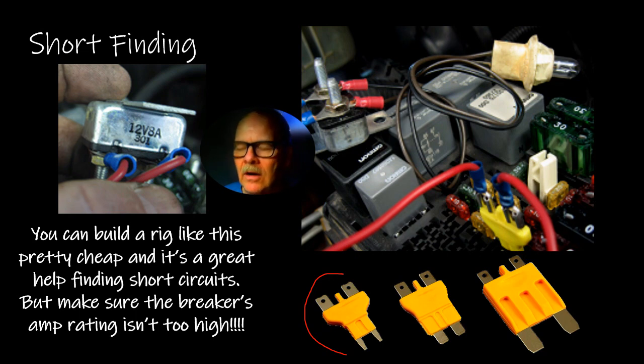The way that works is you connect a light bulb to these two terminals, and you connect these two terminals, which is a self-resetting circuit breaker. You need to make sure the circuit breaker you choose is rated at about the same amperage as the circuit you're checking, because if you put a 30 amp breaker on a 10 amp circuit, you're going to burn wires up. Now if you're checking a 10 amp circuit, I got this 8 amp circuit breaker, so it wouldn't burn the wires up, but it would open and close the breaker when the short was there, you see.